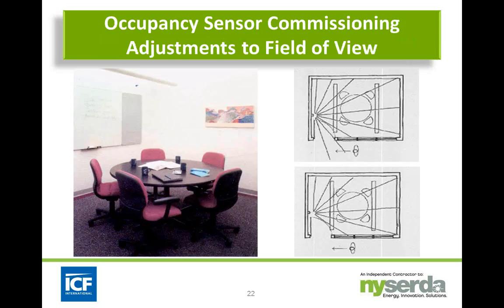Some other ways to adjust field of view: wall-mounted switches are often shipped with little masking devices—a heavier grade of colored masking tape that matches the device color. This lets you blank out segments of the lens so it doesn't see out into a hallway. Make sure you cover that part of commissioning so you don't get false readings into the space.